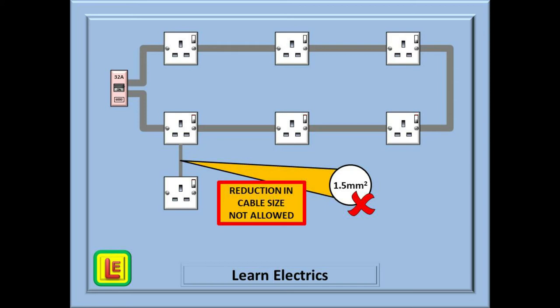Another bad practice is to connect a spur to the ring with a reduced cable size. A reduction in cable size is not allowed for cables that connect to the ring. It is not looking good at the moment. We cannot have spurs on spurs and we cannot reduce the cable size. Well, yes we can, if we do things a little differently.